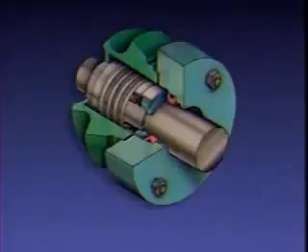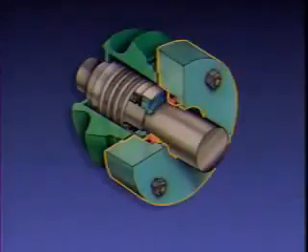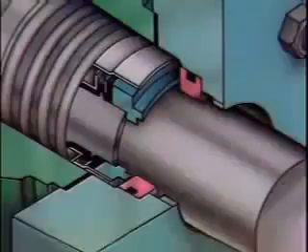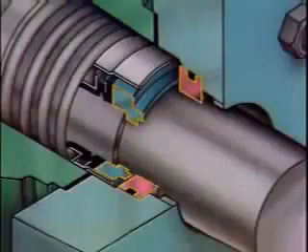Pumps require some type of seal between the pump shaft and the casing to keep process liquids in and contaminants out. Some pumps use packing to seal around the shaft; other pumps use a device called a mechanical seal. A mechanical seal has two basic parts: a stationary element attached to the pump casing and a rotating element attached to the pump shaft. Each element has its own seal ring, and the two rings are positioned close together to form a seal that has virtually no leak-off.